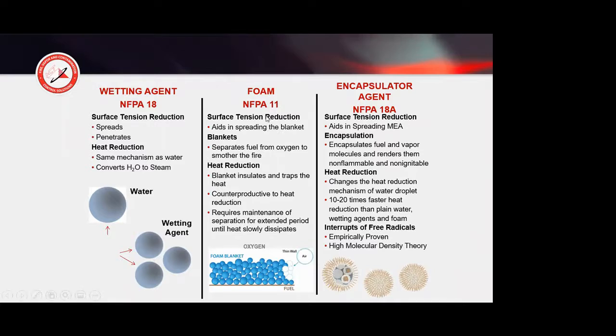With a foam technology, you get surface tension reduction. In the foam standard, it's actually referred to as spreading coefficient, and it aids in spreading the blanket. One of the differences here is you're forming a blanket. So the basic building block, as we see here, of a foam is a thin wall bubble structure or a film, but you have a bubble structure, and we're putting all these bubbles together to form a blanket to separate the fuel from the oxygen and mechanically smother the fire. Again, I've mentioned that we trap in the heat, it's counterproductive, and it requires that we maintain that separation until we can allow that heat to slowly dissipate.